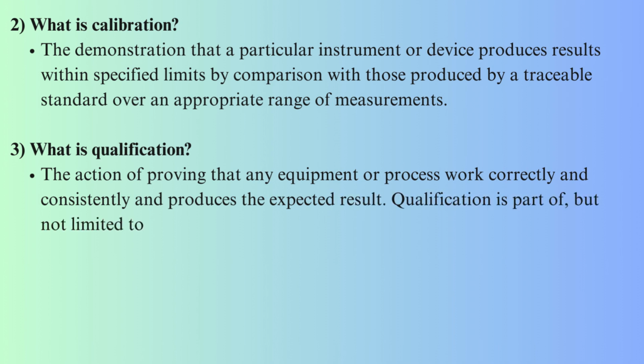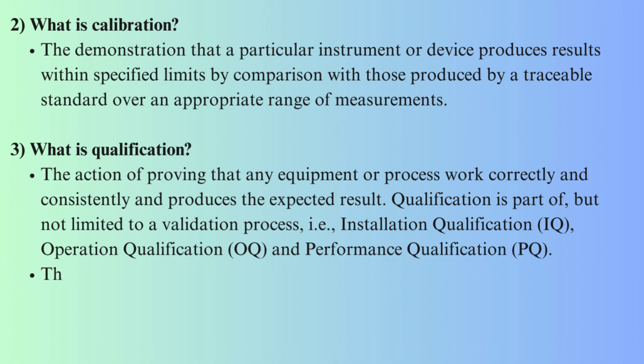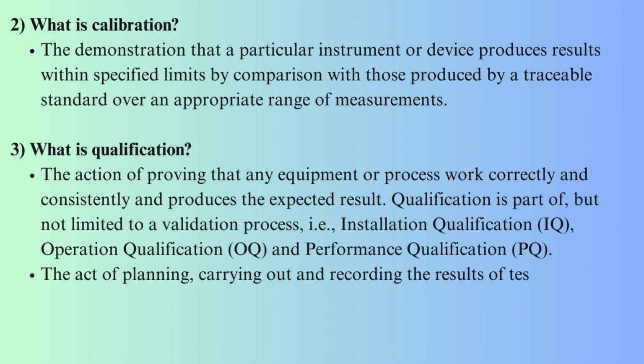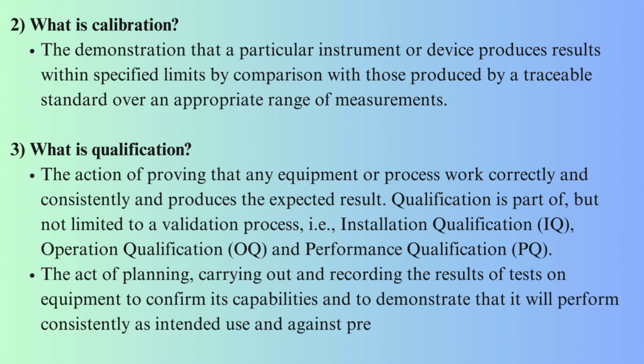Qualification is part of, but not limited to, a validation process: installation qualification, operation qualification and performance qualification. It is the act of planning, carrying out and recording the results of tests on equipment to confirm its capabilities and to demonstrate that it will perform consistently as per intended use and against predefined specification.